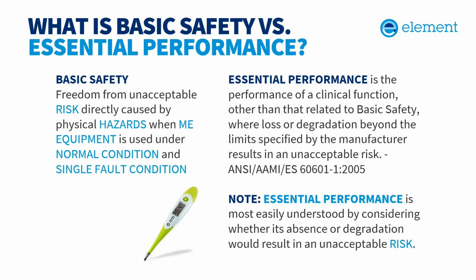So while 60601 talks about risk and basic safety and essential performance, what are those? Basic safety is essentially that the product or system remains safe to use for the patient and operator and bystanders, even during a fault. An example of this is I tested an implantable defibrillator to AAMI TIR69 dipole testing for immunity to cellular signals. And during this test, this implantable defibrillator unintentionally shocked. That could definitely cause a safety issue both during installation of the product by the doctors and nurses, and also to the patient during their normal daily activities, being unintentionally shocked. That's a critical safety issue.